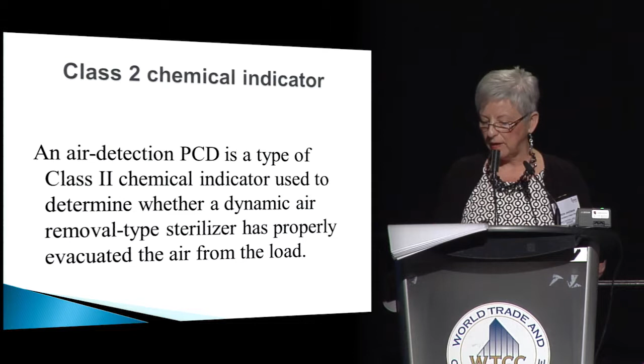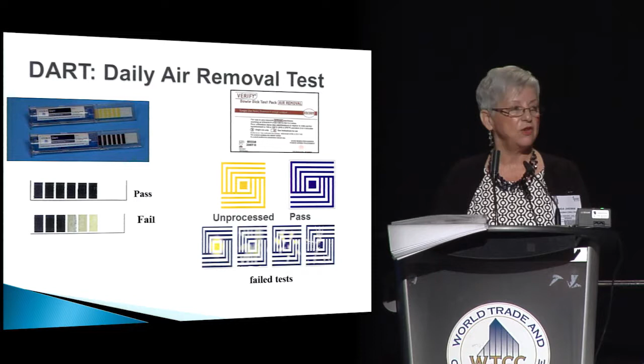So if you look at the picture, you can see the chemical indicator is yellow and white, and that's prior to going into sterilization. Once it goes into the sterilizer, the chemical changes to black. And if there's an inconsistency in the black, that's a failure. So you want to take that particular sterilizer out of service and find out what the issues are around the air. Because if the air is present, of course, you can't sterilize it.